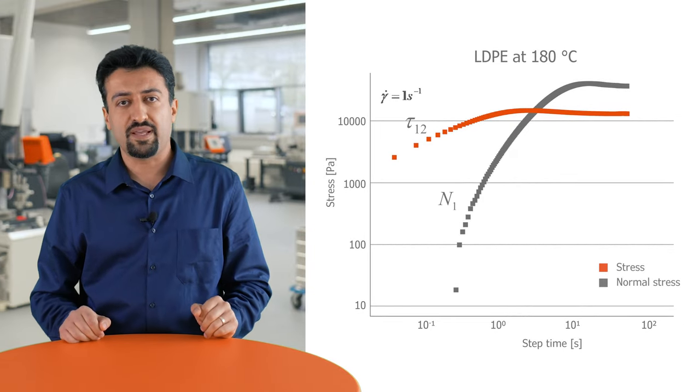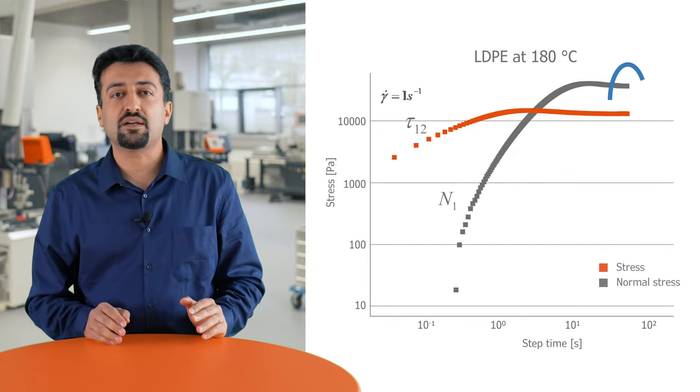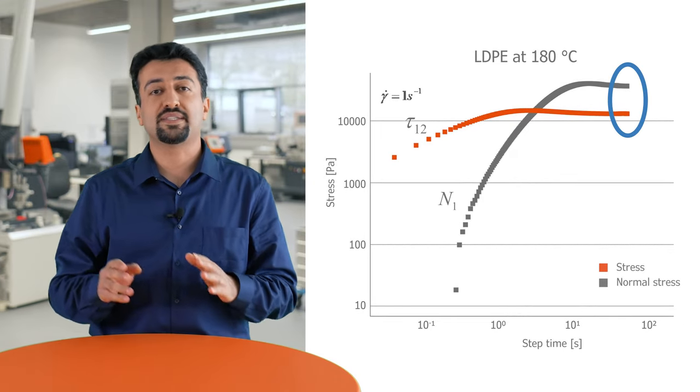I'm Masoud from Gottfried application department. Normal stresses are commonly measured in rotational rheometers in transient shear experiments. The sample is placed between parallel plate or cone and plate geometry and depending on the shear rate some amount of time is needed until the stress values reach steady state.